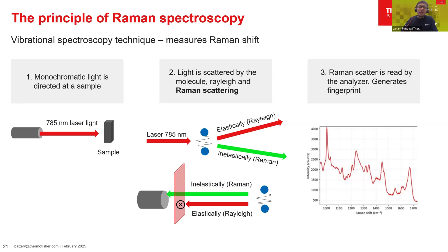So what are some of the advantages of Raman spectroscopy? Let's look at that on the next slide. One of the biggest advantages of Raman spectroscopy is that it is extremely fast and usually provides results in milliseconds to seconds. It is also a non-destructive technique and requires no sample preparation, unlike some of the other analytical techniques, making it suitable for in-process monitoring. Depending upon the optics used, it can be used to measure the sample through the containers and packaging materials, such as glass and plastics. It is also extremely data rich as well. Additionally, Raman spectroscopy can provide quantitative and qualitative information and can measure multiple analytes with single scan.